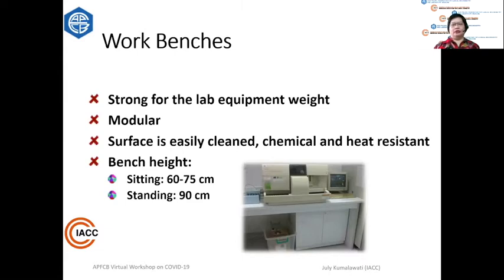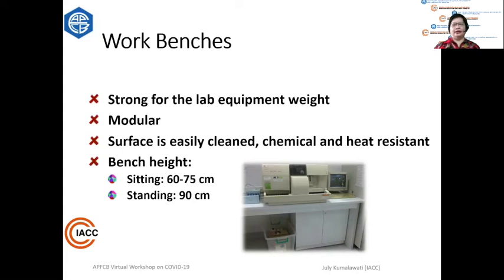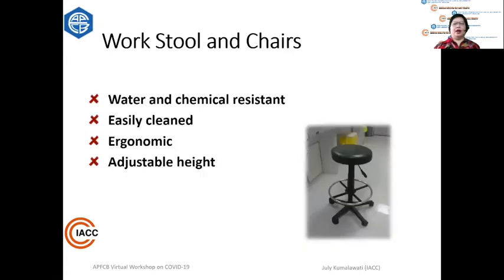Work benches must be strong enough to bear the weight of instruments. Preferably modular, so if you change the layout you can move modules around. The surface should be easily cleaned, chemical resistant, and heat resistant. The bench height for sitting position work is around 60 to 75 cm, and for standing position work, it can be 90 cm. Work stools or chairs should be water and chemical resistant, easily cleaned, and ergonomic — ideally height-adjustable.